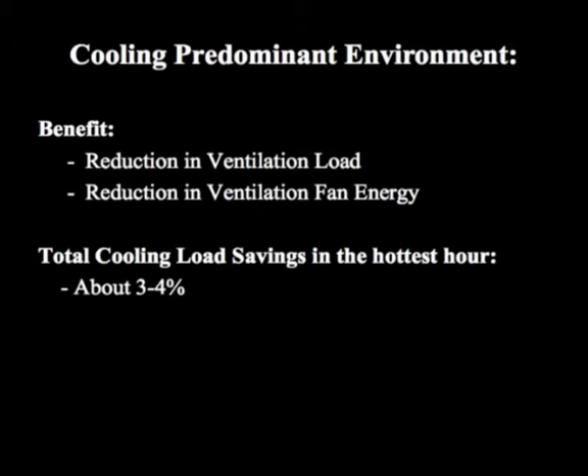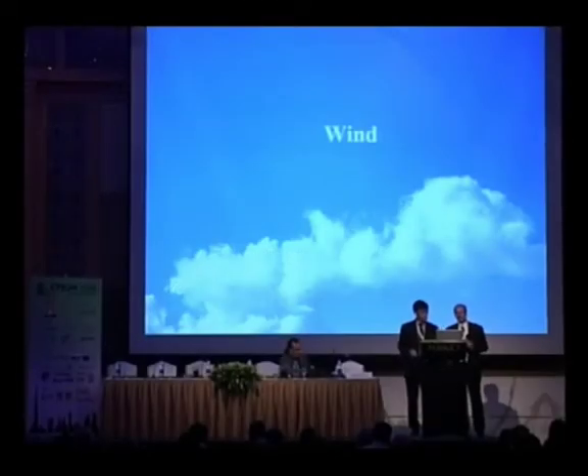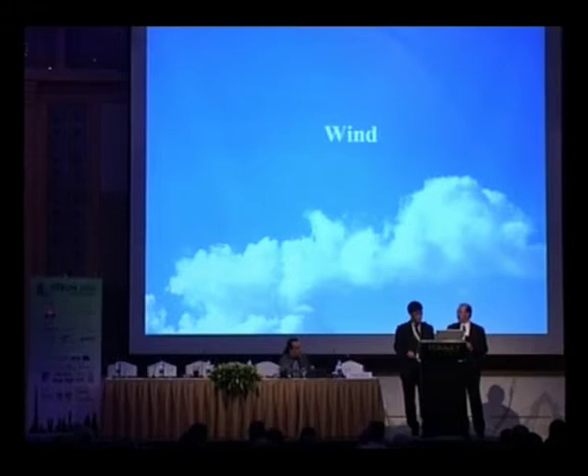That's actually another benefit for tall buildings, especially at the top. The total cooling load saving in the hottest hour is the lowest, about 3 to 4%, simply because the air is less dense to deal with. From an architectural standpoint, this means we try to locate fan rooms higher up in the building and take advantage of that by pushing the cooler air downwards.